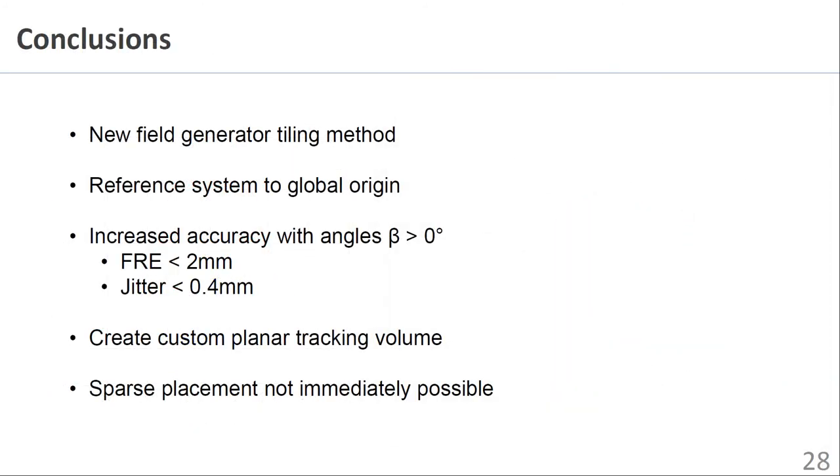In summary, this work describes a new field generator tiling method for electromagnetic tracking. The method operates by referencing additional field generators to a common origin. We show that introducing tilt angles between adjacent field generators reduces positional and jitter error. The work allows custom tracking volumes to be built, although sparse tiling of field generators is not immediately possible with this design.